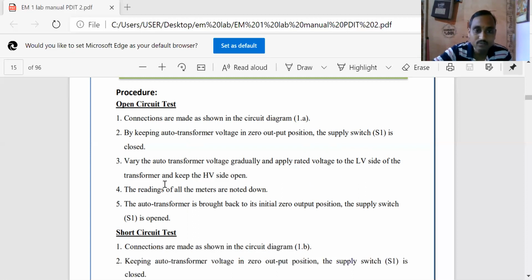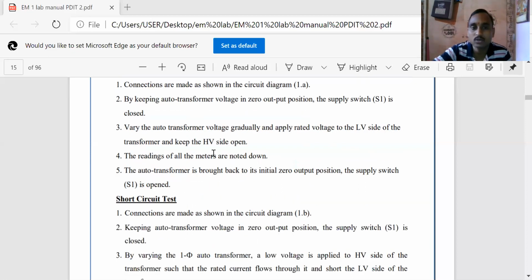Keep the high voltage side open. The secondary side should be open circuit, and the readings of all the meters are to be noted. What are the meters you have connected? Voltmeter, ammeter, and wattmeter. That is V0, I0, and W0. You take 3 readings of the meters. All the readings of the wattmeter are noted down.